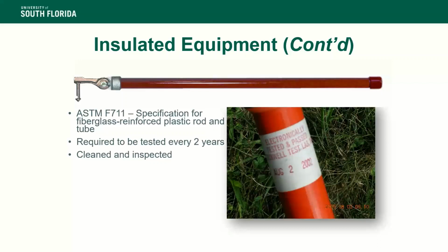Another one is the insulated equipment here. We're looking at this fiberglass reinforced plastic rod. The key here is not just making sure it's labeled, but to test it. I know out in the industry, manufacturers change equipment. One of the things I want to bring out to the participants this morning is that I always go back to the manufacturer's recommendation. When you buy something, open it up and don't just issue out the equipment. Read what the manufacturer says and see if it's required to be tested every 2 years and put it on a preventive maintenance program, or you can send it out to get it tested if it's required.